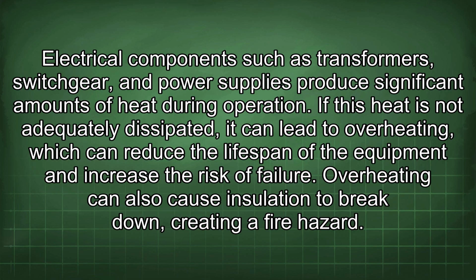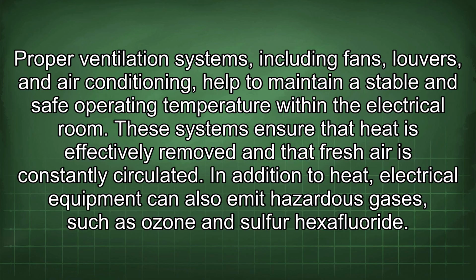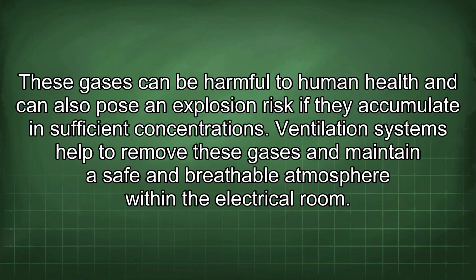Overheating can also cause insulation to break down, creating a fire hazard. Proper ventilation systems, including fans, louvers, and air conditioning, help to maintain a stable and safe operating temperature within the electrical room. These systems ensure that heat is effectively removed and that fresh air is constantly circulated. In addition to heat, electrical equipment can also emit hazardous gases such as ozone and sulfur hexafluoride. These gases can be harmful to human health and can also pose an explosion risk if they accumulate in sufficient concentrations. Ventilation systems help to remove these gases and maintain a safe and breathable atmosphere within the electrical room.